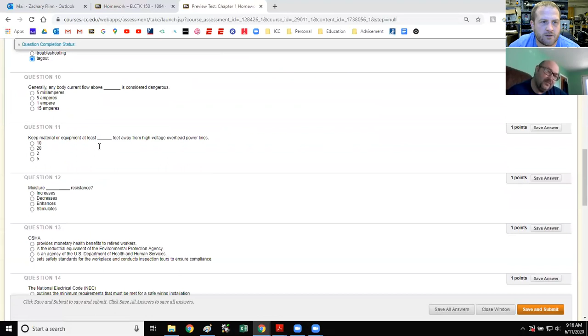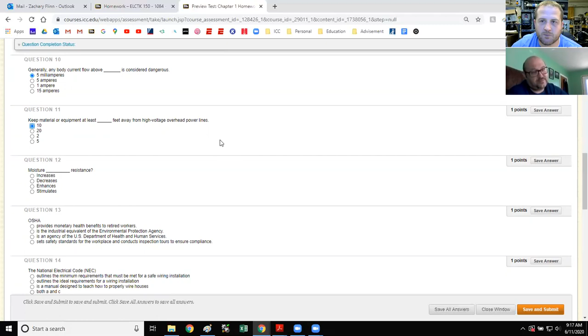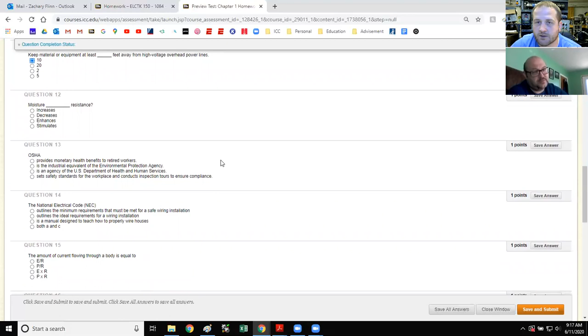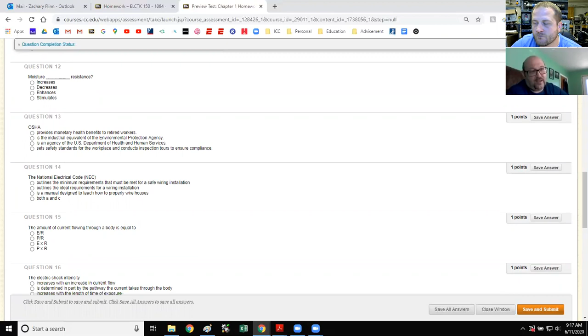Keep material or equipment at least how many feet away from high voltage? It says 10 feet. I think that's a rule of thumb, but like Ameren has their own clearance depending on if it's vertical, horizontal, and all that. Personally, if I'm in a bucket truck, I don't like to be anywhere near the stuff. When we were in the oil field, we had to move generators that were taller than the lines, so they either had to remove them, or we had to use a laser to see how tall they were. Out there they wanted at least 15 feet from the top of the generator, so they'd have to take the poles out all the time for us to get in there. Yeah, I bet.